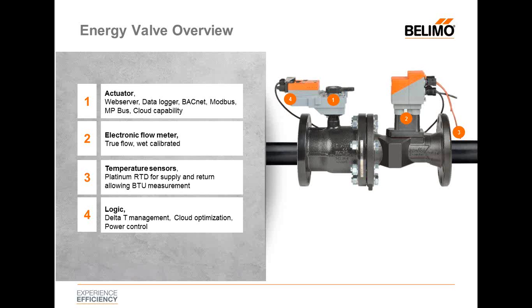We have something called delta T management. What delta T management does is maintain the delta T across the coil — basically getting the coil operating back at the design delta T. System inefficiencies will cause excessive flow rates through a coil, such as not being balanced or pressure-dependent valves overflowing. At a point on the power curve of the coil, the coil will begin to saturate. So with the delta T manager, we begin to modulate the flow rate to get to the appropriate level and get the coil operating back at the design.